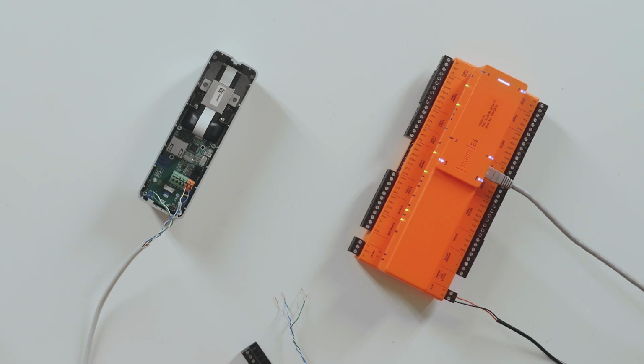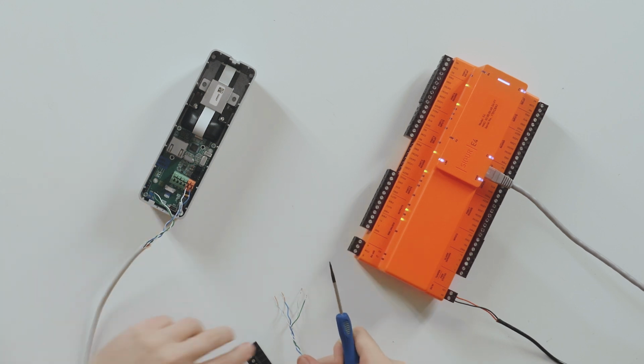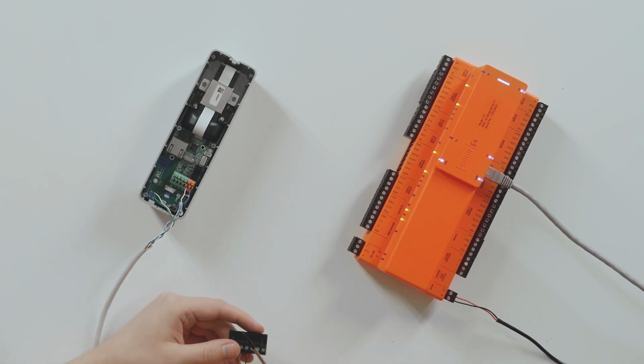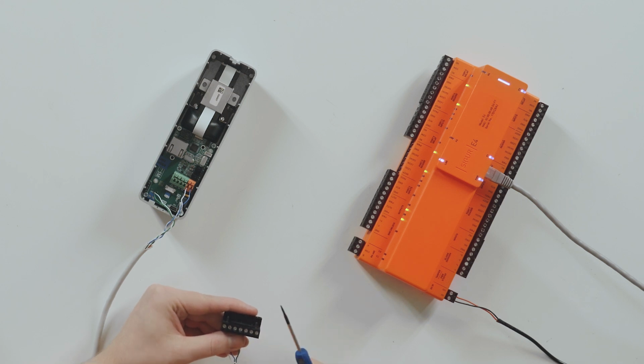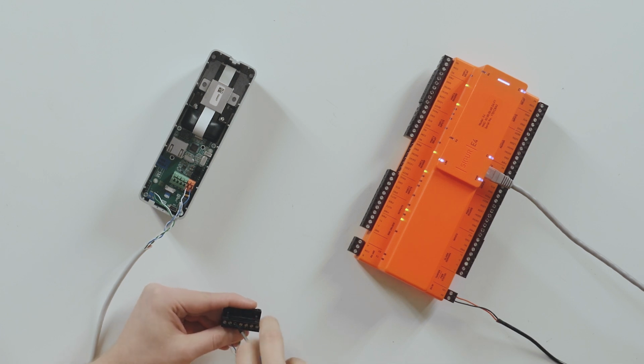Let's move on to the integration setup and start by connecting the reader to the controller. To transmit information to the controller, the reader must be connected via the Wiegand interface. For this purpose, the Biosmart 5M reader board has Wiegand 0 and Wiegand 1 terminals. Connect the Wiegand 0 and Wiegand 1 terminals of the Biosmart reader to the Data 0 and Data 1 terminals of the controller port. For correct data transmission, the common 0V wire of the Biosmart 5M reader and the GND terminal of the Sigur controller port must be paired with the wires of the Data 0 and Data 1 lines.